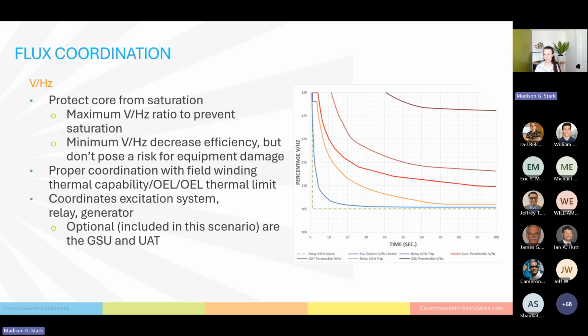And the core of the generator, if the magnetic field increases to a certain point, or that flux increases to a certain point, the core of the generator will saturate. And that can create thermal runaway in the generator, which is devastating. Don't want that to happen. So we have a maximum volt-hertz ratio, which helps prevent that saturation. There is a level of that volt-hertz ratio where the generator loses efficiency and doesn't operate very well, but it doesn't really pose a risk for equipment damage, so we don't really worry about protecting for that. We really just worry about that maximum threshold to prevent saturation.